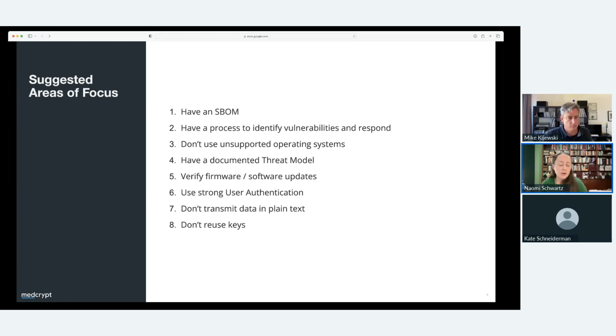Yeah, so I know a lot of companies are asking about having an SBOM. What exactly does that mean? Do I have to have an SBOM? Do I have to show that SBOM to FDA? Do I have to show it to my customer? Yes, you have to have an SBOM. You should know what's in your software, in your device. You should be sharing that with FDA. The reg now requires it for cyber devices, but the guidance recommends it for all devices that have those three characteristics: it has software, or it could have vulnerabilities, or it can be connected to the internet. You should just have an SBOM because you need to be able to monitor for vulnerabilities.